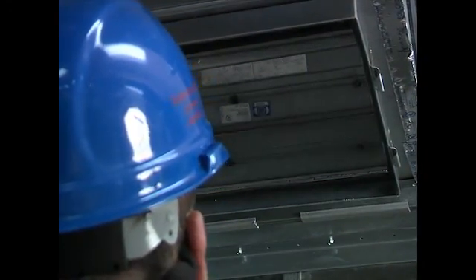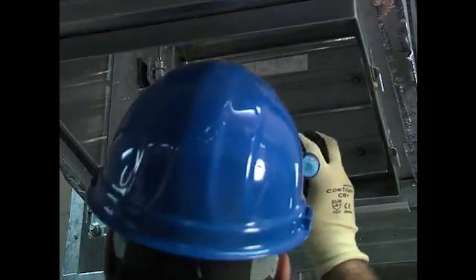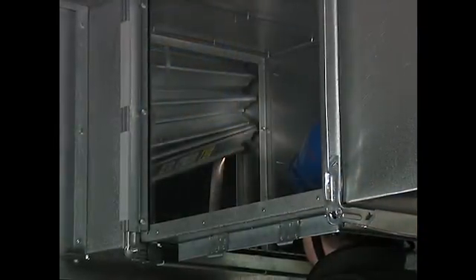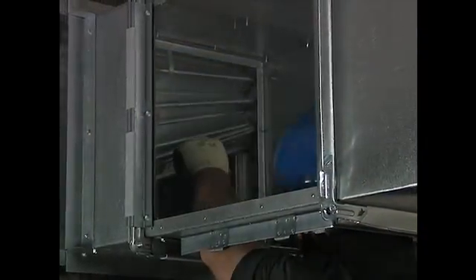Testing dampers to make sure they close as completely as they can, preventing or slowing fire or smoke from spreading through the system. Something as simple as a screw improperly inserted in the framework can keep a damper from closing all the way. A broken or missing linkage clip can prevent safeguards from performing properly even though the motor is still running.